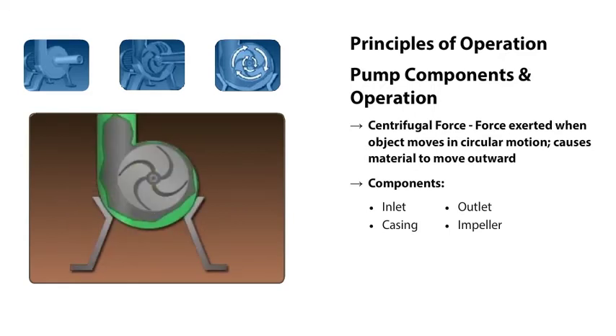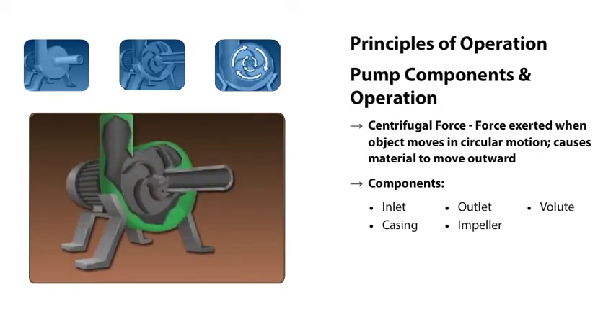The pump's casing is designed so that the area around the impeller creates a gradually widening spiral channel. This widening channel is known as the volute. Since this pump has only one impeller and one volute, it is referred to as a single-stage pump.